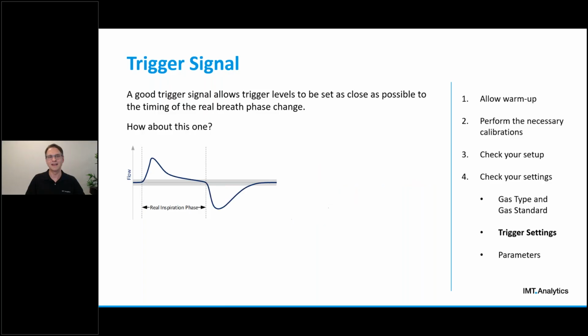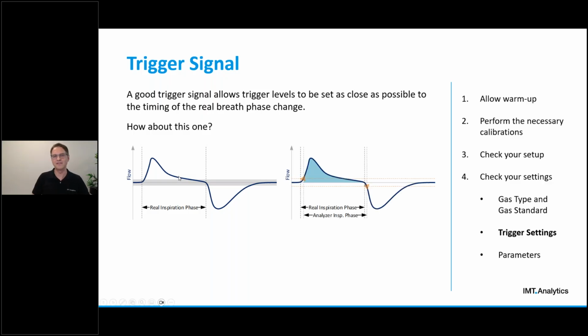So let's have a look at the second example to understand this topic a little bit better. So how about this one? Let's see how this one looks. Here, it turns out that it's quite good, because we have a positive flow through the flow channel in the inspiration phase and a negative flow through the flow channel of our analyzer during the exhalation phase. And this is a very typical situation in ventilator testing applications.